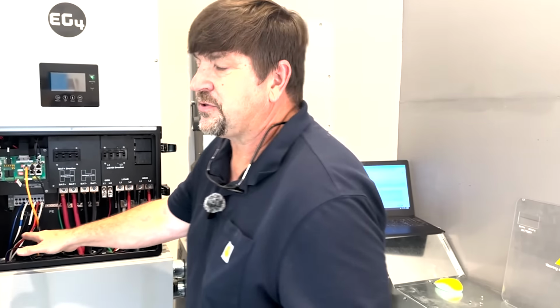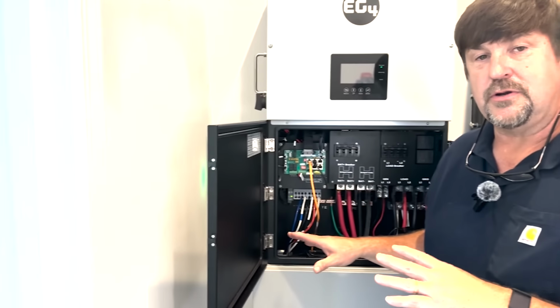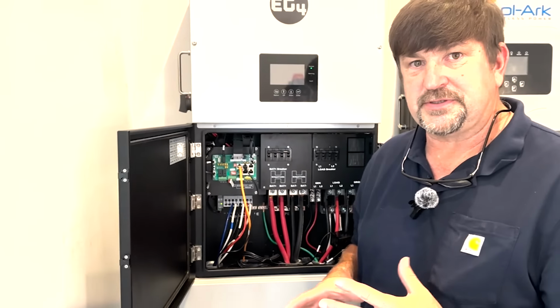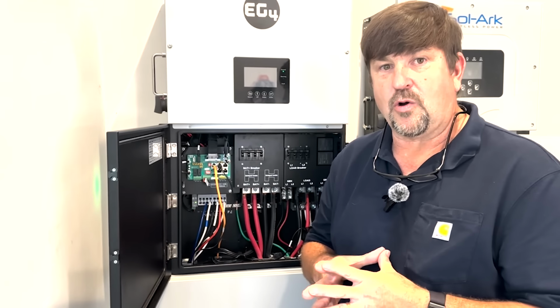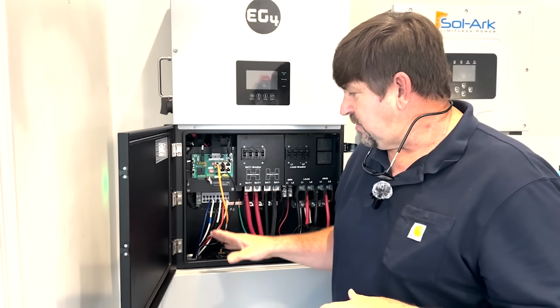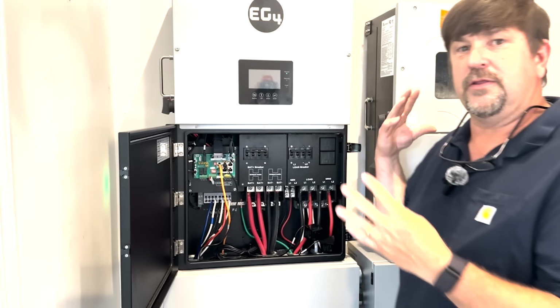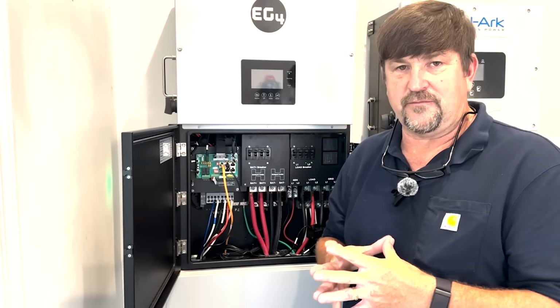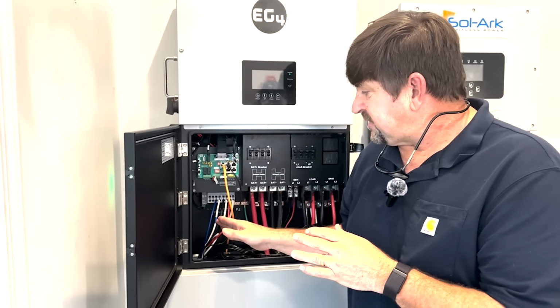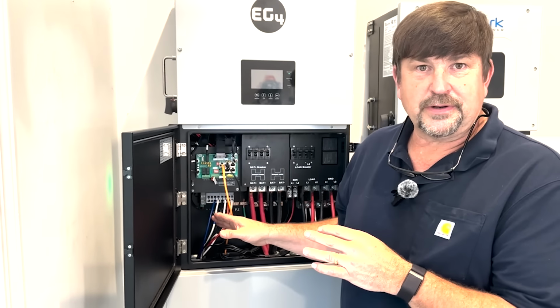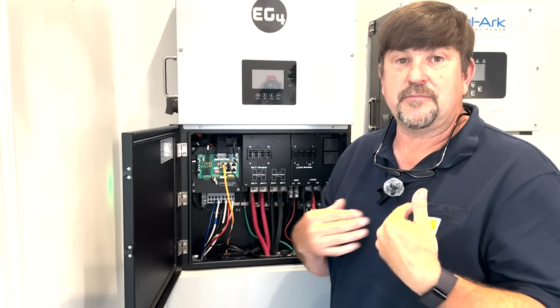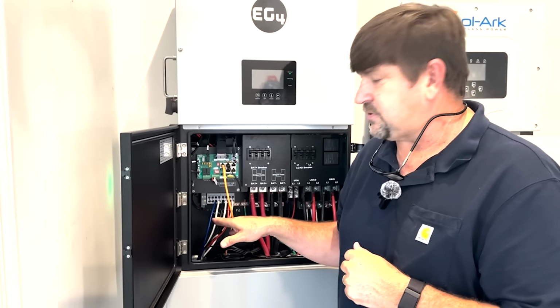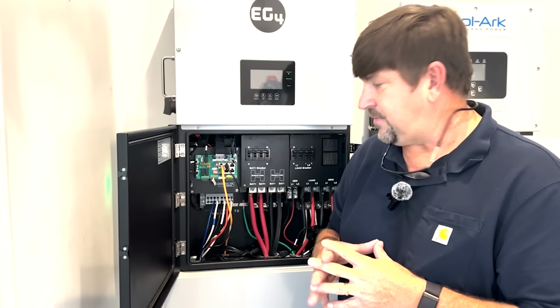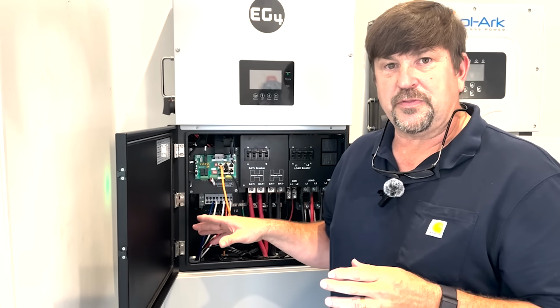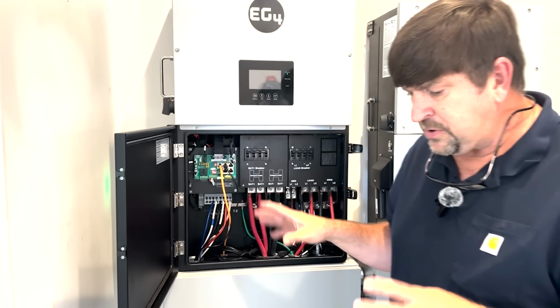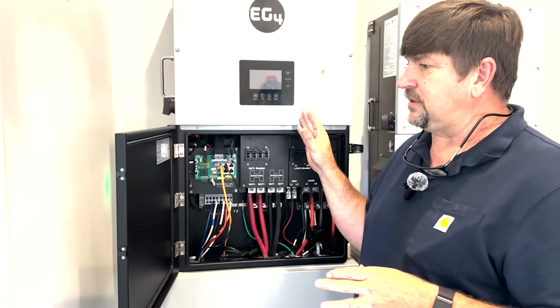I don't know how they wire 21.6. Remember, when you do your sizing, you have to compensate for where you are and how cold it gets on the coldest day, or you can blow up either one of these machines if you exceed that VOC input. So I don't know how they get 21K, maybe on the equator, but not in Pickens, South Carolina. They can't put 21K on there, not with the panels I'm using. Be careful about thinking you can put that much PV on this machine.